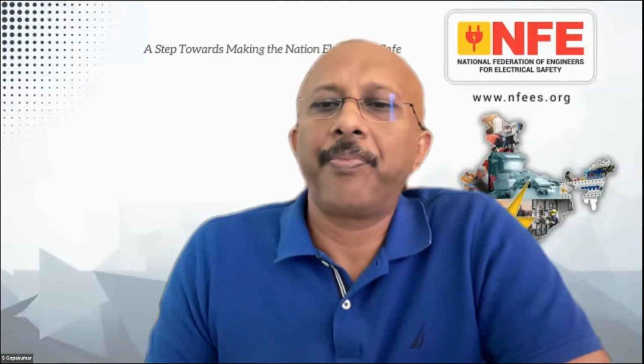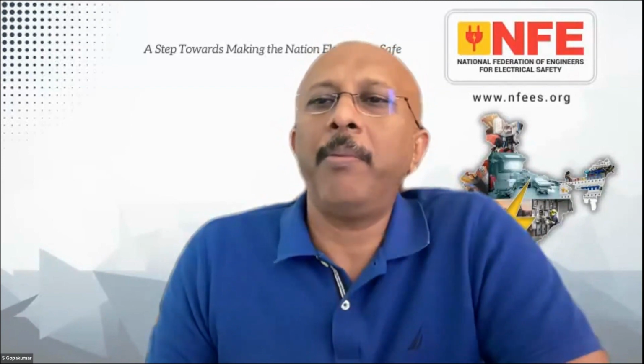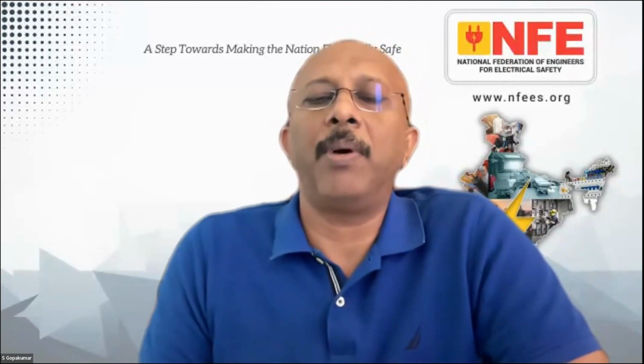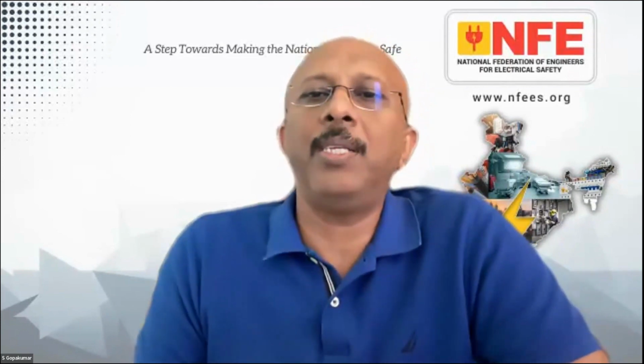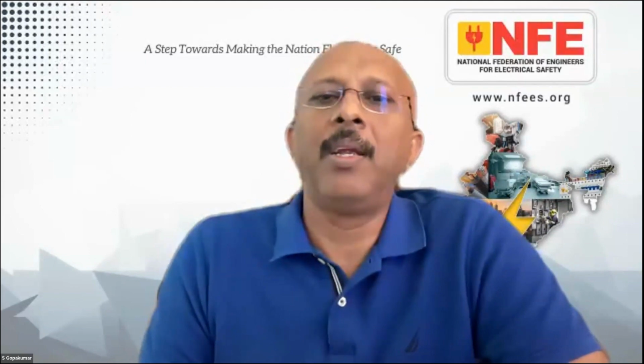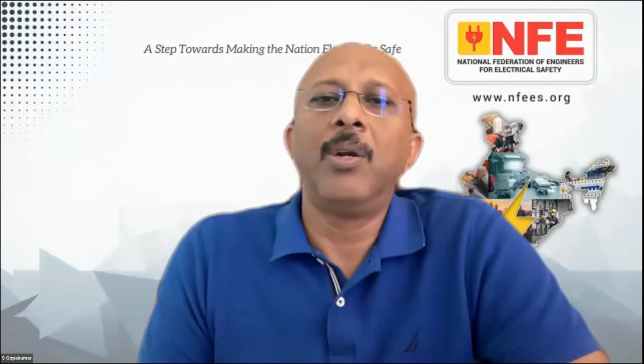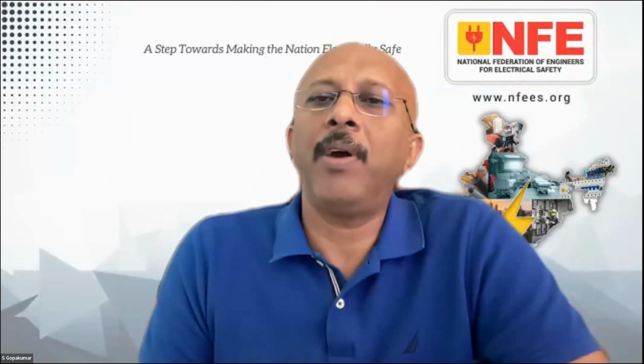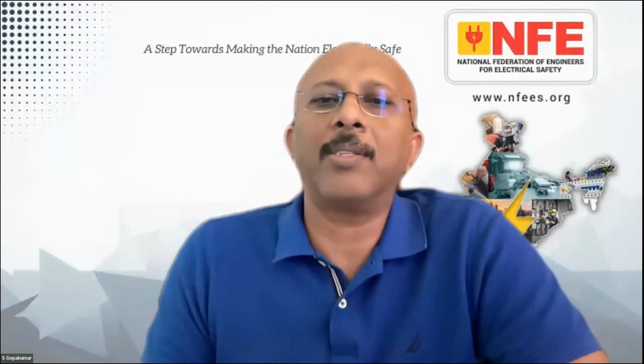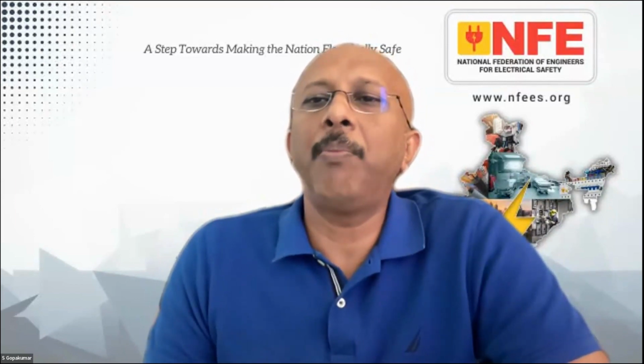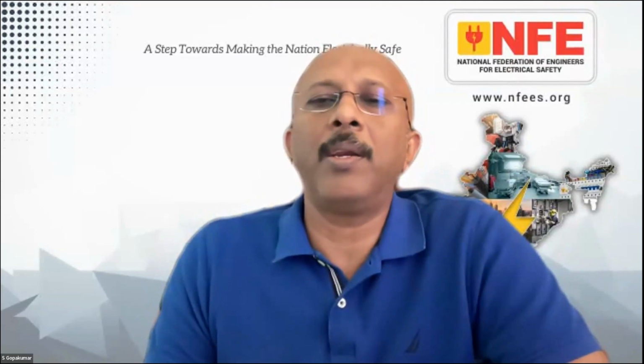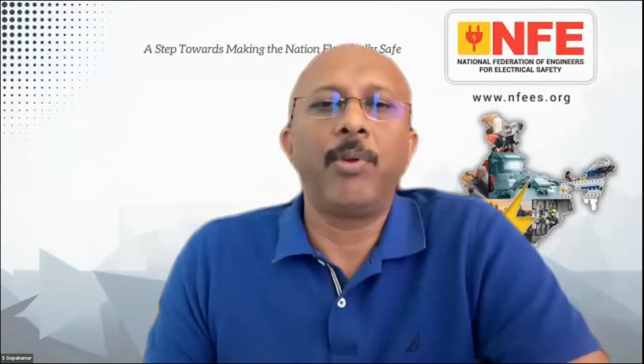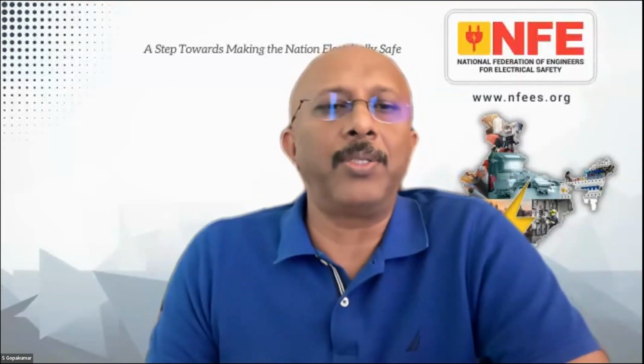So we have a question from an anonymous attendee. Normally we don't take up questions from anonymous attendees, but still, let us see. My question is that fault loop impedance measurement definitely has a relation with the linear length of the circuit wire and the size of the conductor. Do we have data on the length of wiring restrictions in a building to keep earth fault loop impedance within range at the time of planning and execution of the work? The answer is very simple, sir. This is also related to voltage drop. Your circuit should be within the voltage drop limits.